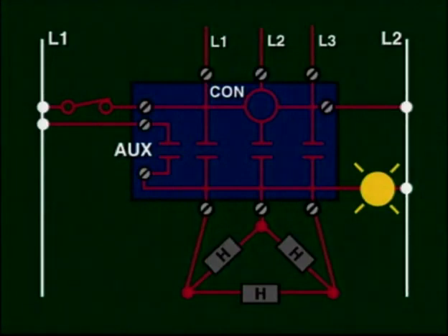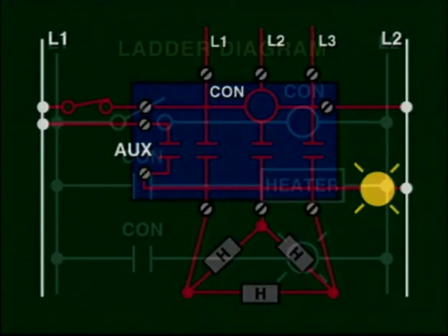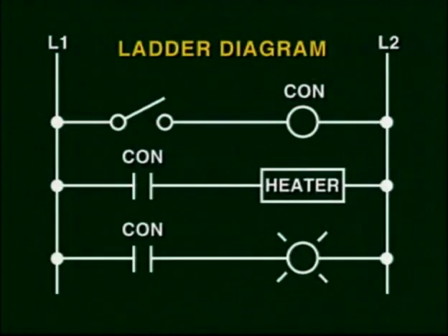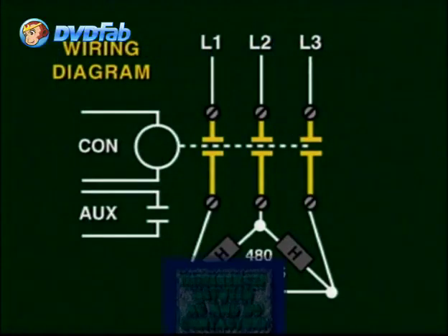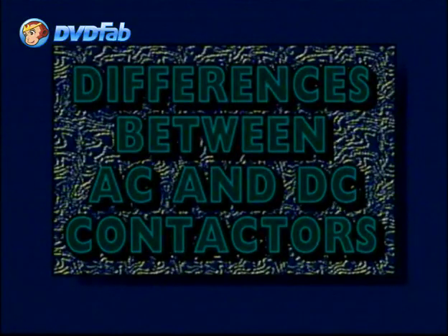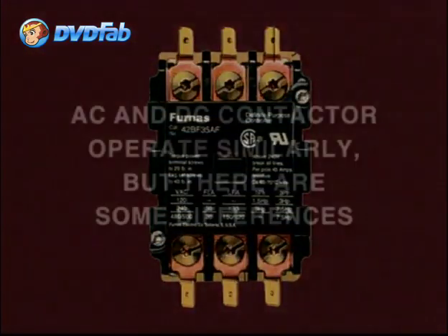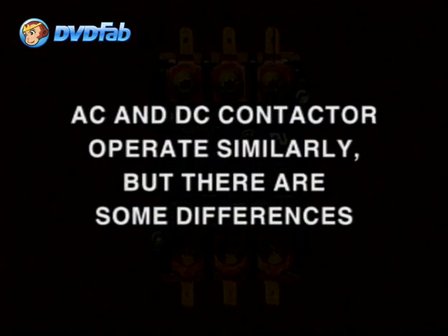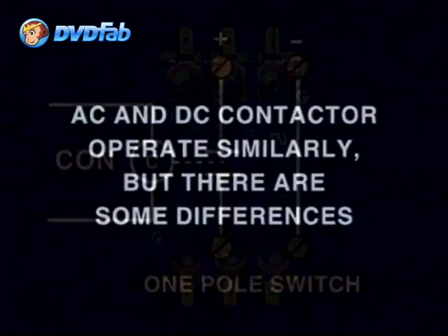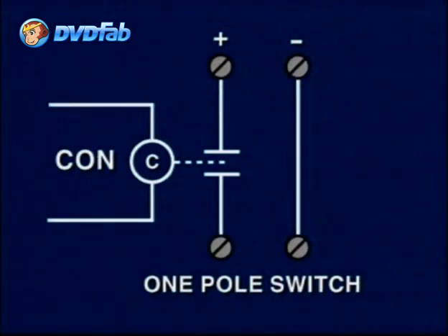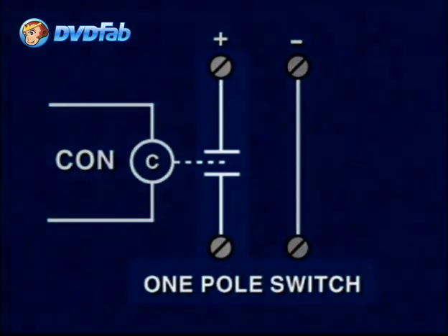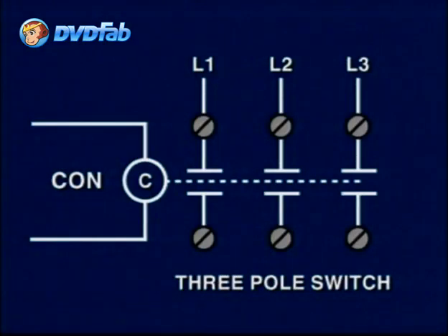Obviously, this type of circuit representation is cumbersome and confusing. That is why we simply represent it like this in the ladder diagram for control purposes, and like this in a wiring diagram. Even though AC and DC contactors operate in a similar manner, there are some differences between the two. In DC contactor applications, we may switch only one of the power lines, thus requiring only one set of contacts, or a contactor having only one pole. In three-phase circuits, it is necessary to switch all three lines, thus requiring three poles.